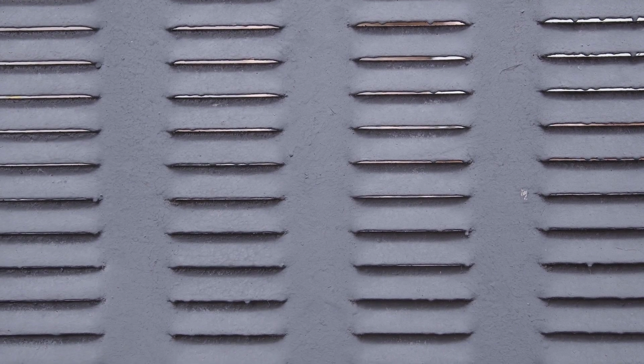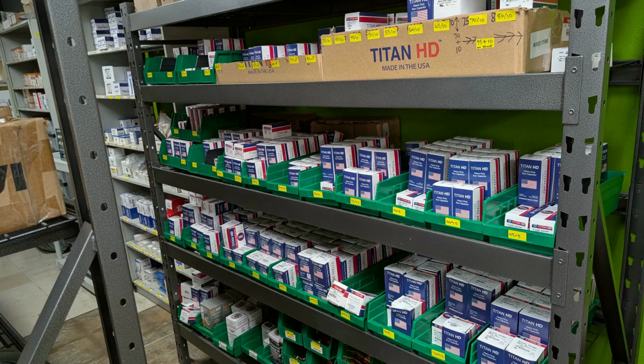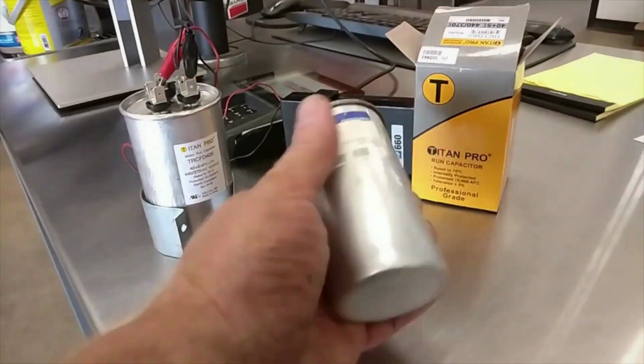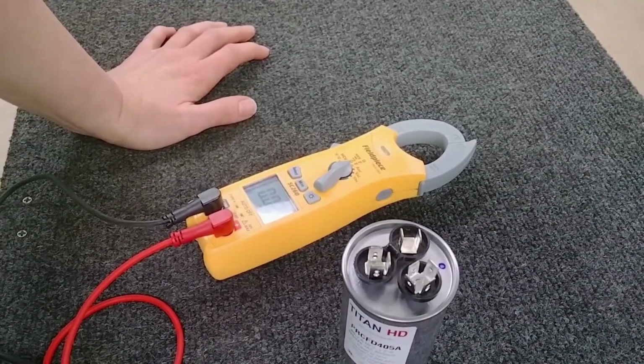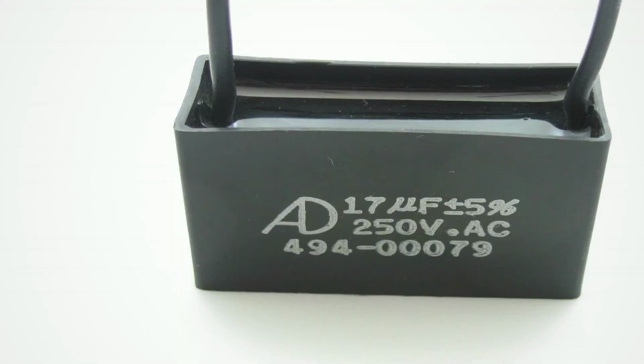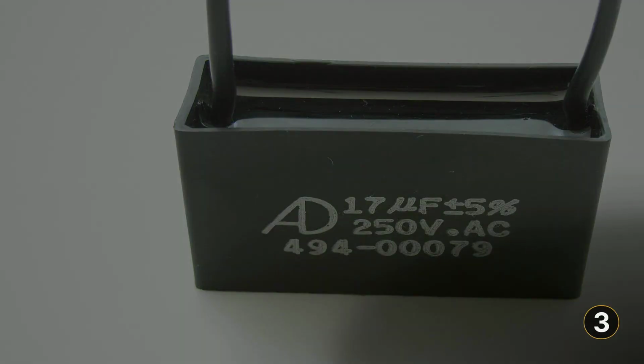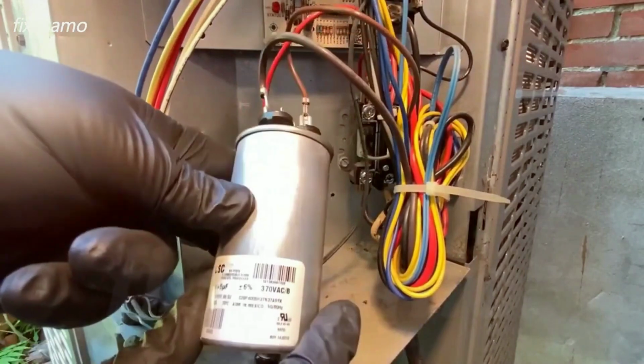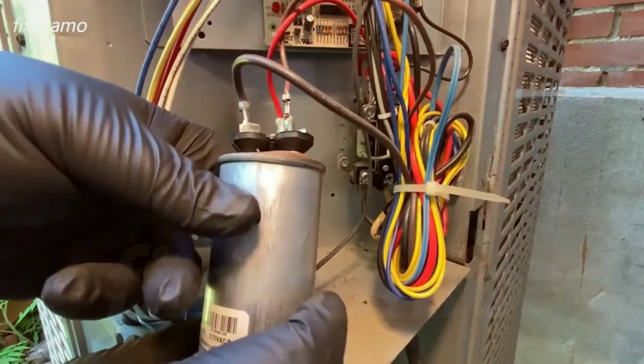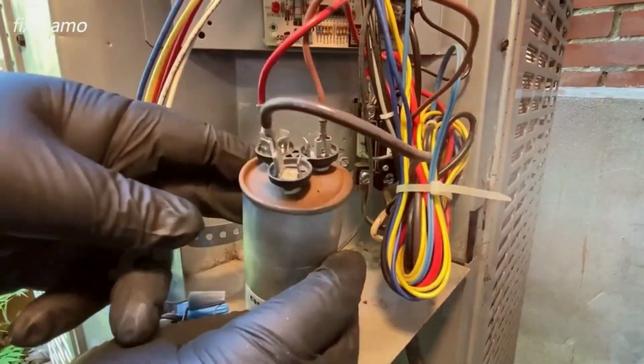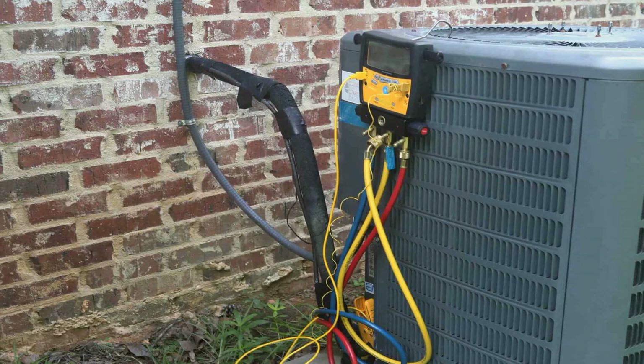If the label is faded or missing, check the wiring diagram typically taped inside the unit's access panel, or look up the model number on the outdoor condenser unit online. HVAC supply houses carry the widest selection at the lowest prices and can often match your specs same day. Amazon is convenient, but requires careful verification. Confirm every number before ordering. Big box hardware stores carry limited inventory at higher prices and may not stock your exact rating. Know your 3 numbers before you buy anything. That knowledge is the entire difference between a successful repair and a compressor problem.